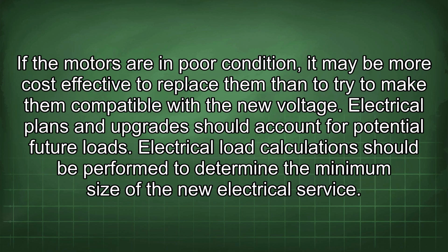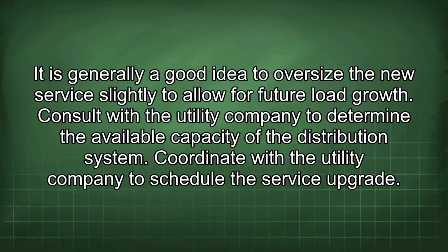Electrical plans and upgrades should account for potential future loads. Electrical load calculations should be performed to determine the minimum size of the new electrical service. It is generally a good idea to oversize the new service slightly to allow for future load growth. Consult with the utility company to determine the available capacity of the distribution system. Coordinate with the utility company to schedule the service upgrade.